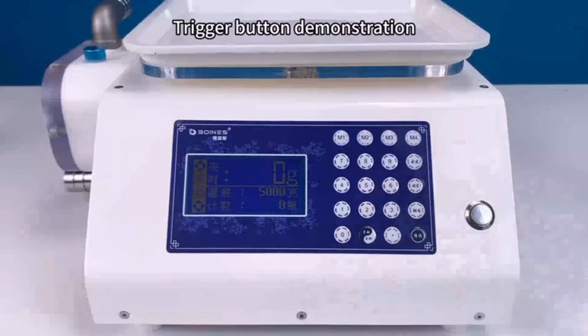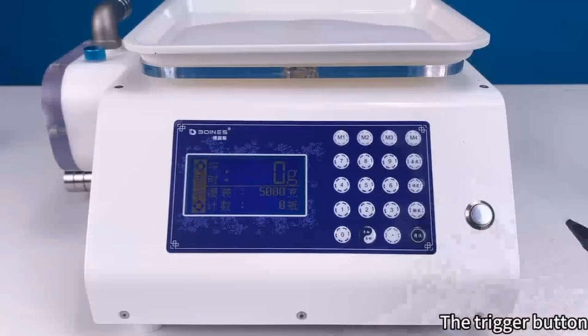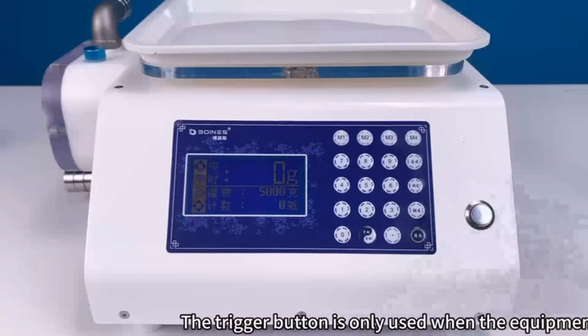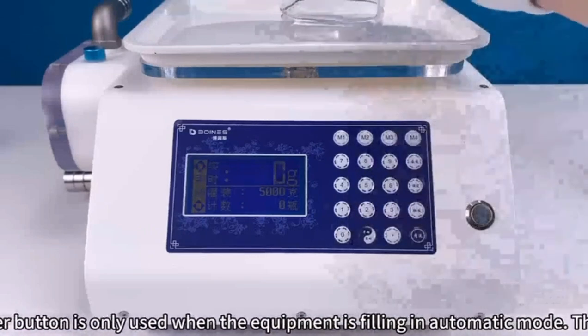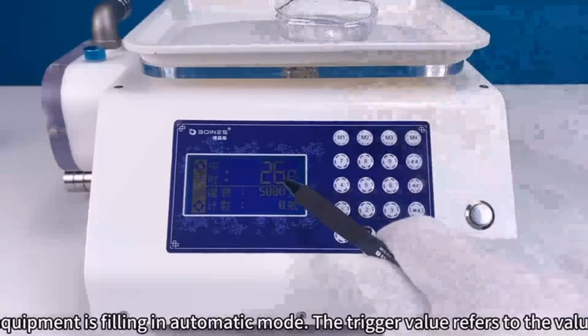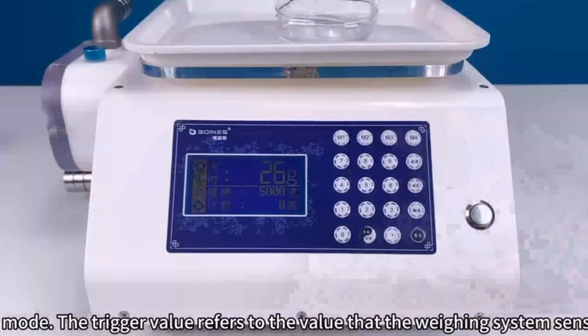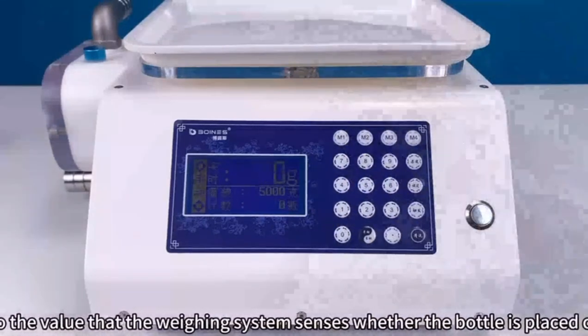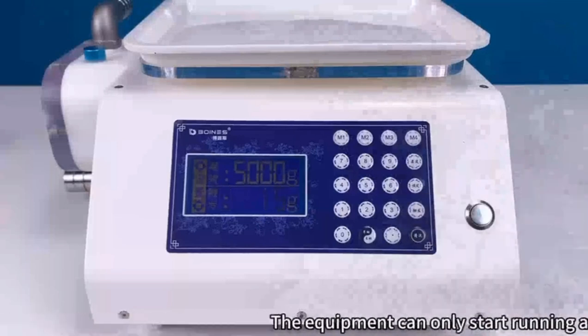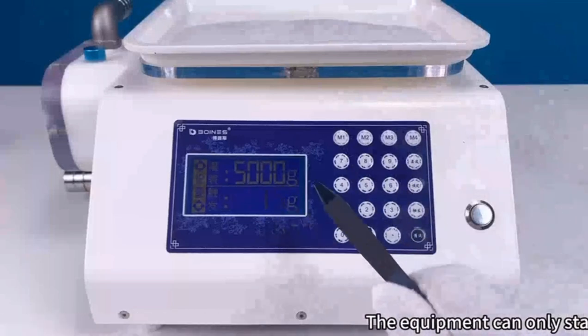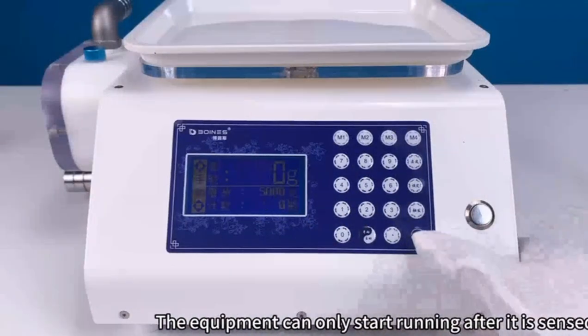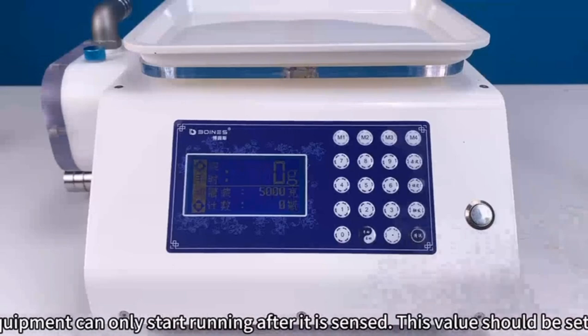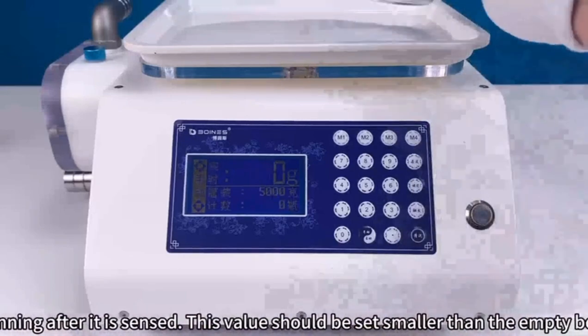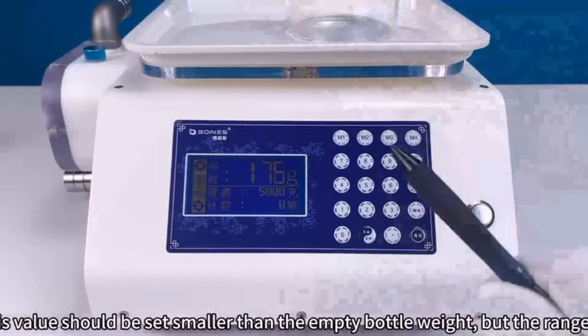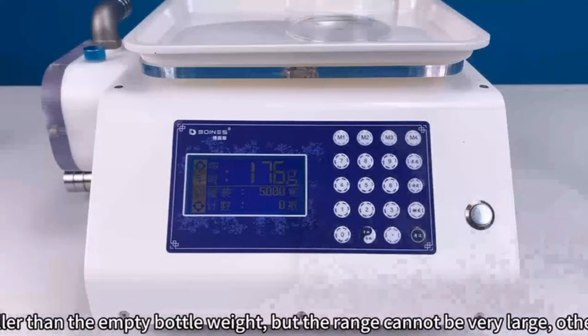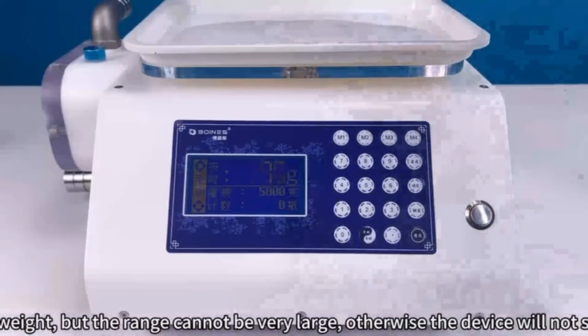Trigger button demonstration. The trigger button is only used when the equipment is filling in automatic mode. The trigger value refers to the value at which the weighing system senses whether the bottle is placed on the weighing pan. The equipment can only start running after it is sensed. This value should be set smaller than the empty bottle weight, but the range cannot be very large. Otherwise, the device will not start filling in automatic mode.